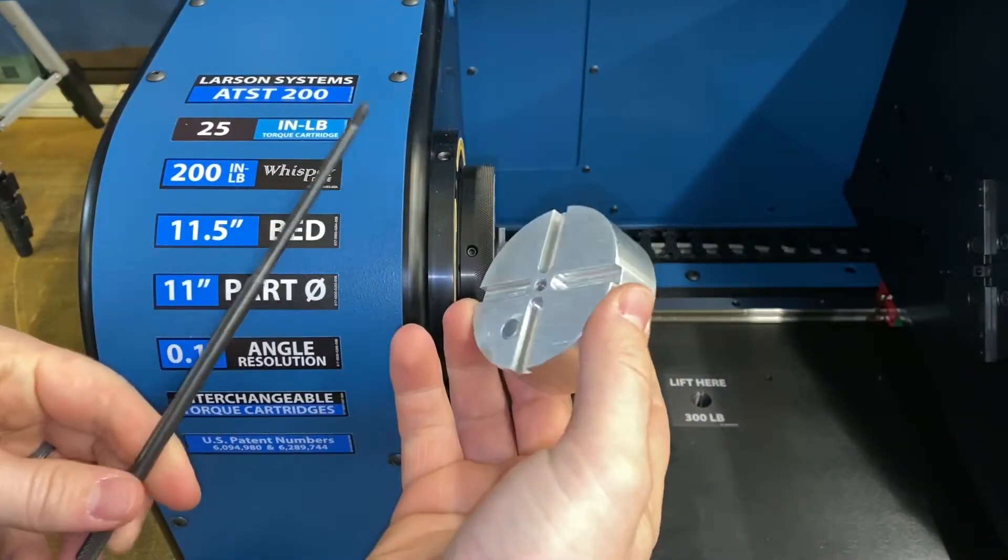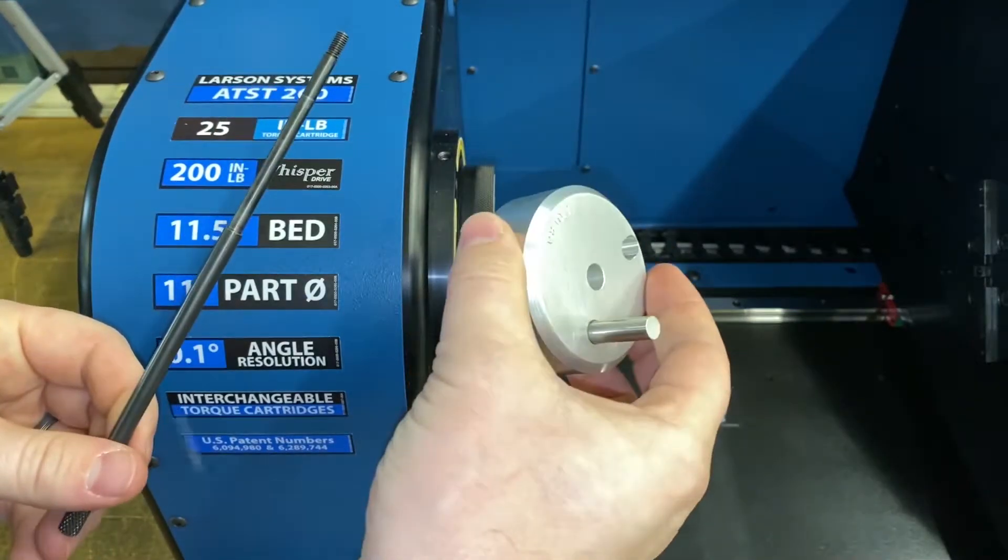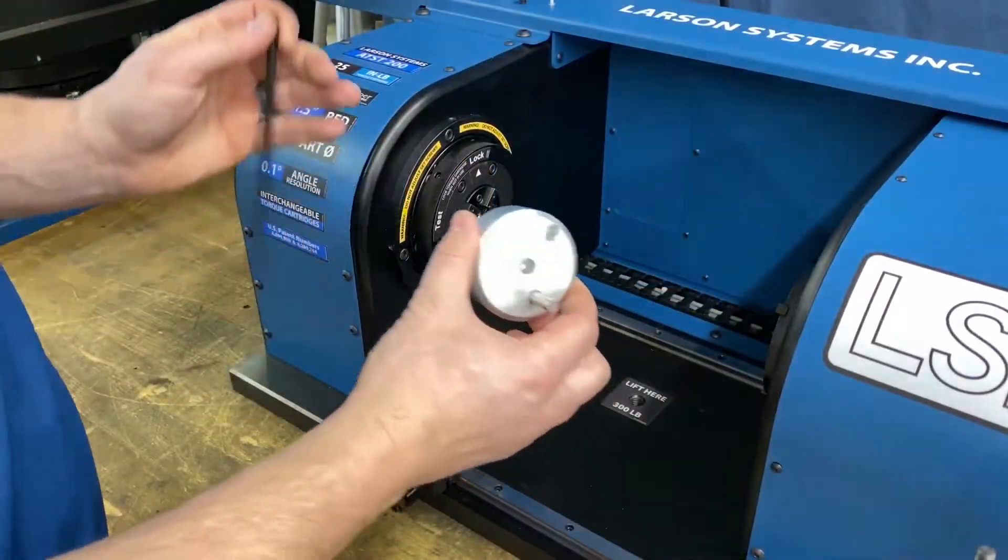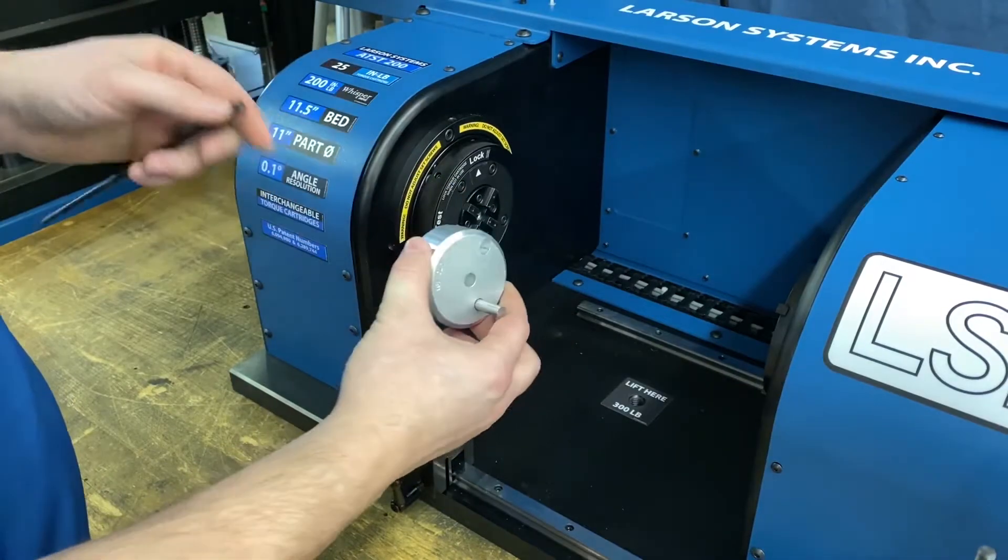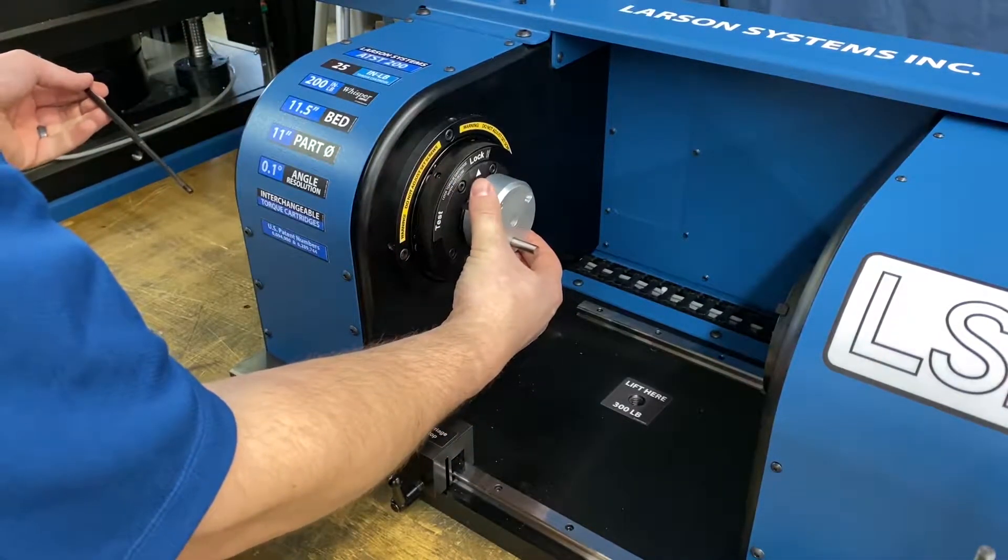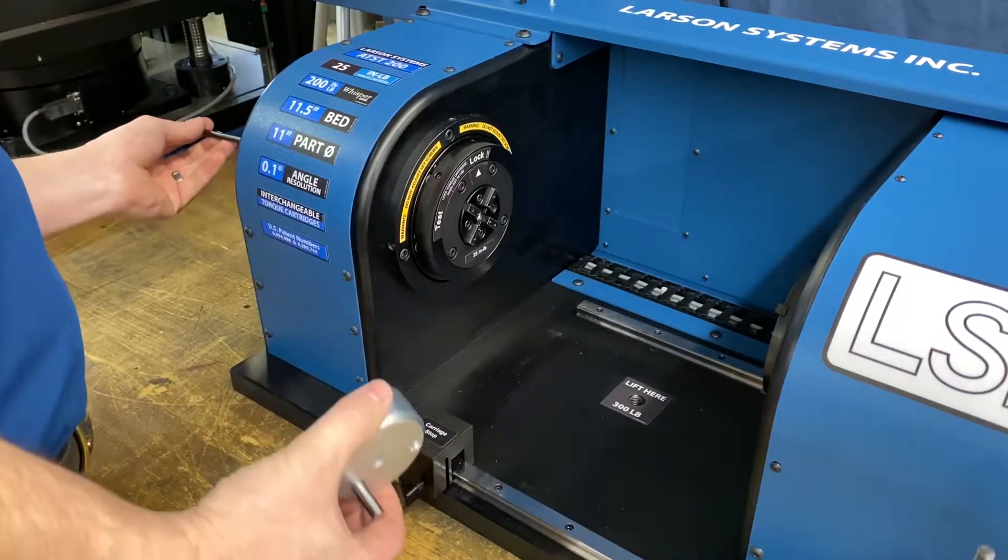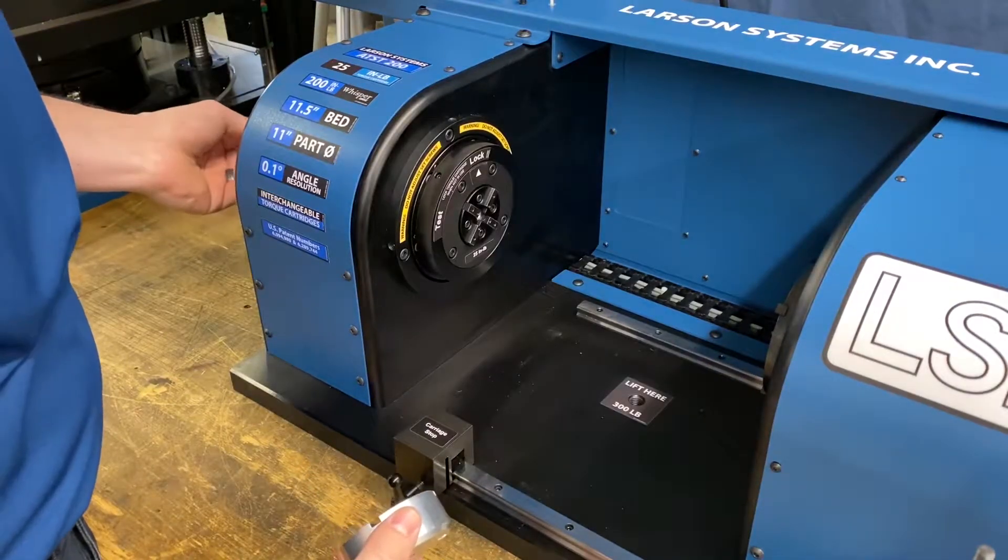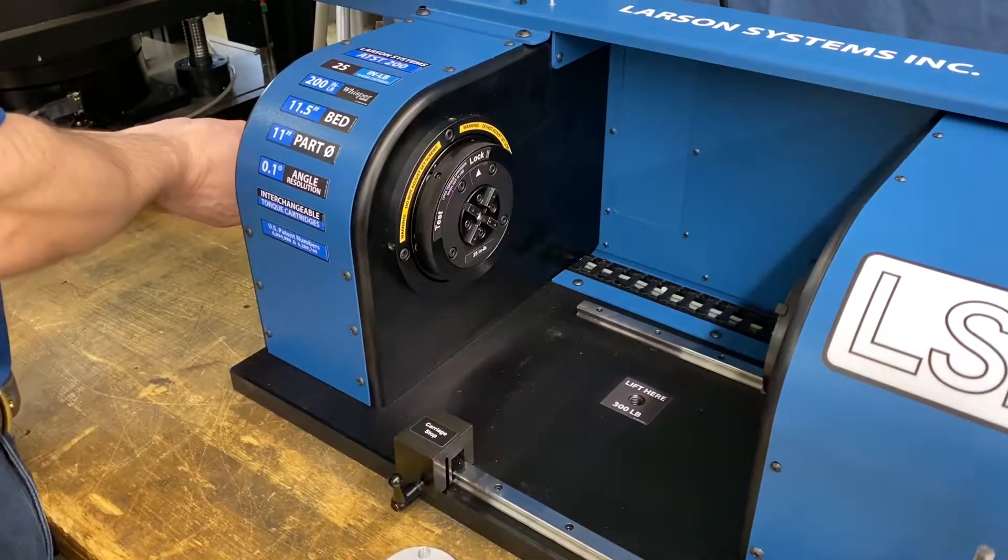Here is some custom tooling for the torsion spring tester. We're going to show you how to set it up. This is the homing key, the homing hole. You're going to put that on the torsion cell right there, and you're going to use the draw bar to tighten it.